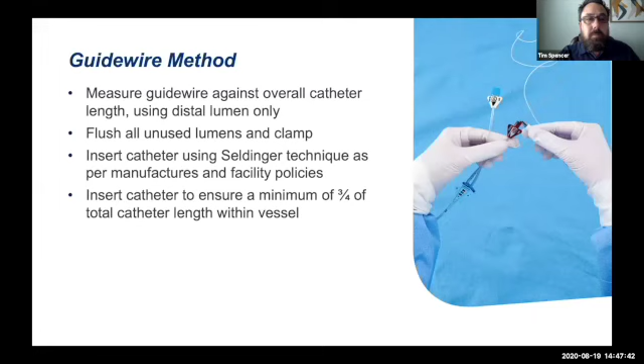So we retract the catheter, and this is a better close-up photo where you can see the end of the J-wire tip is actually just sitting right at the end of the catheter. If that was extended further past that and the J-loop was outside, our catheter tip may be up to maybe 1 or 2 centimeters possibly too short if there's too much wire advanced out of the end of the catheter.